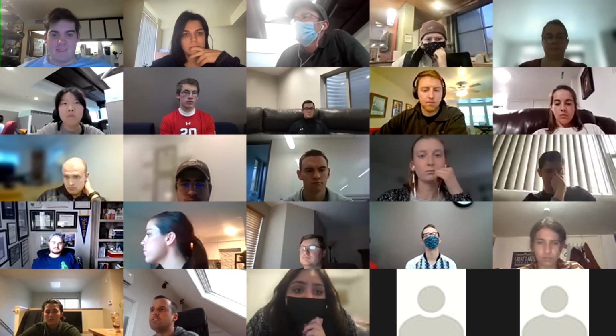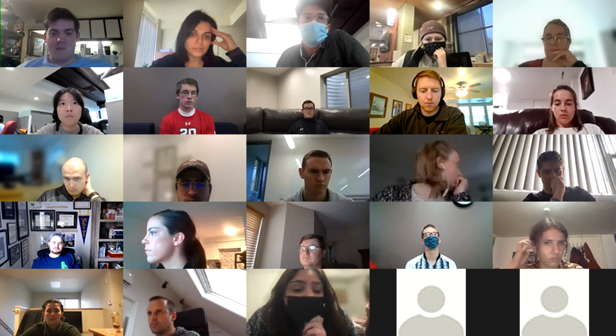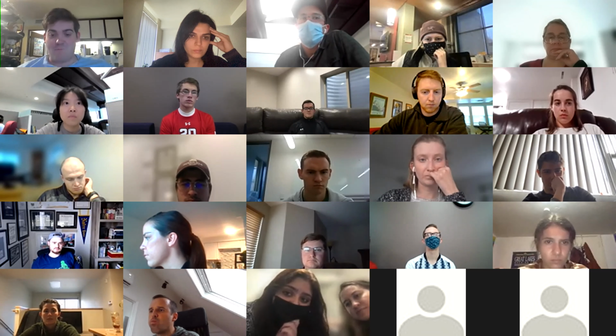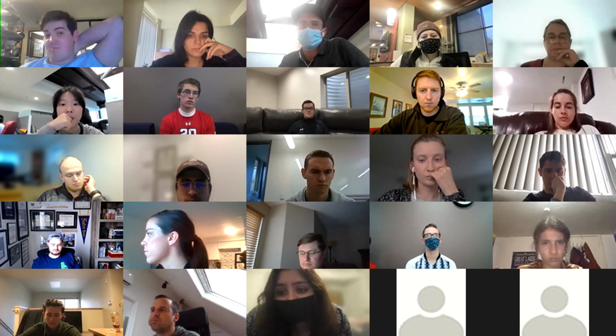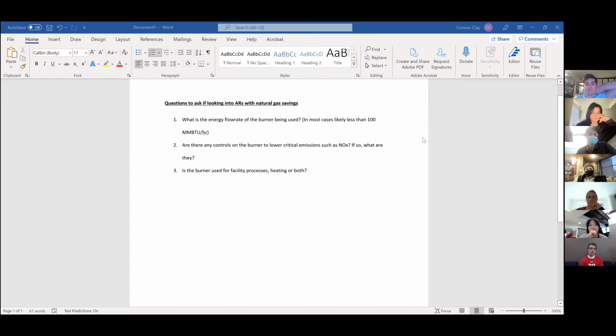Also, another thing I wanted to show really quick is a small list of questions that I feel need to be asked when looking at natural gas burners. These are the three really key questions that you need to have an answer to before you do a natural gas assessment recommendation. What is the energy flow rate? Because then you'll be able to decide between large and small. Are there any controls on the burner that lower critical emissions, such as NOx? If so, what are they?